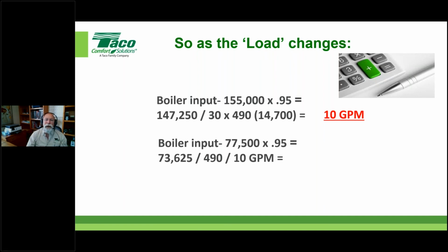Then this is how to do the math to anticipate what your new temperature differential is going to be. You take the net and you divide it by your constant that you're using, typically 500, in this case 490, and then by the GPM that you originally designed at. Now we can anticipate a 15-degree delta T. So under a half load condition, I get half of my delta T. But at least a 15-degree delta T is a lot better than 3 or 2 or 5, which is what we see in a lot of these conditions. And again, we want those delta T's to be as wide as possible at any given time. There are limitations there, like I mentioned, on bench conditions, etc.